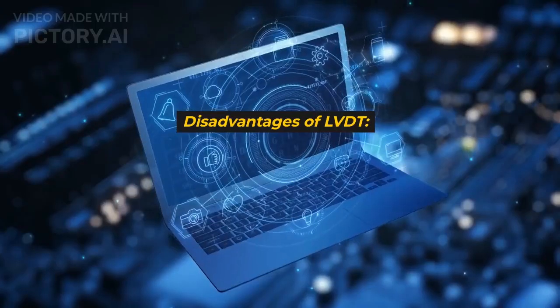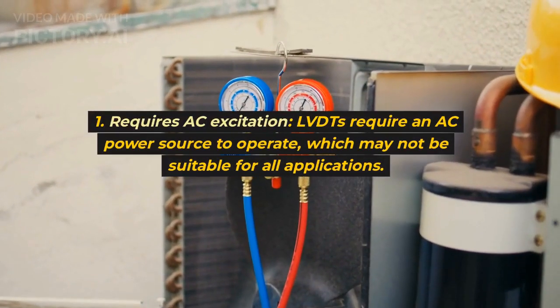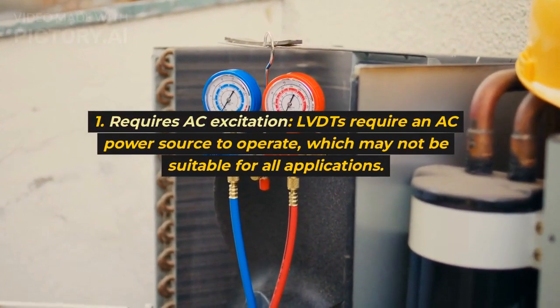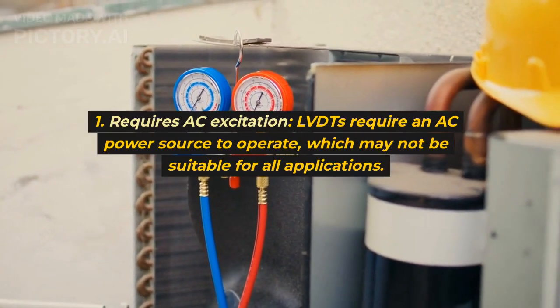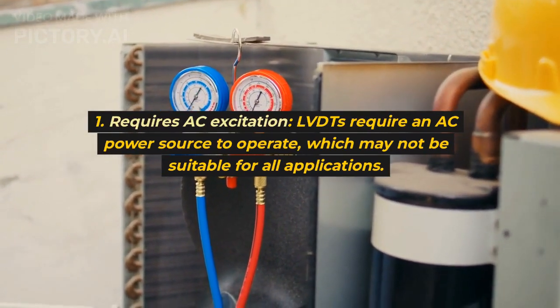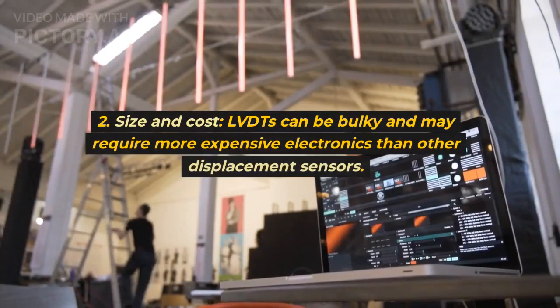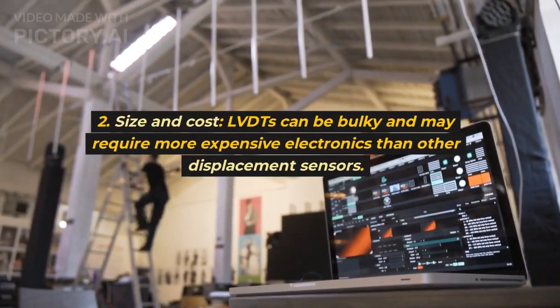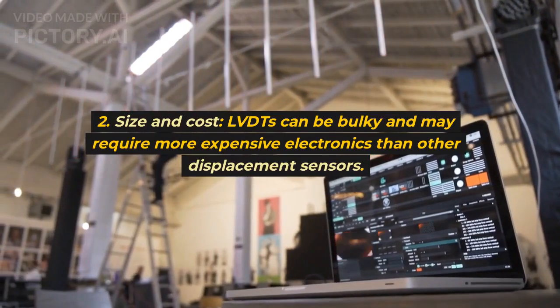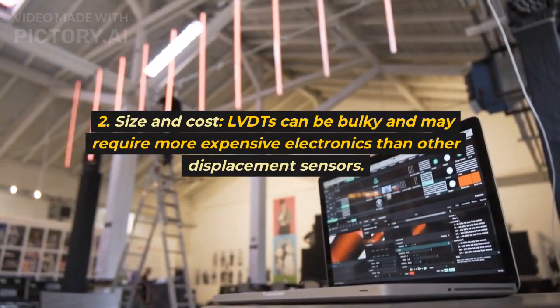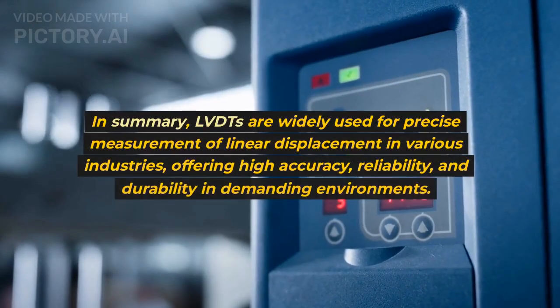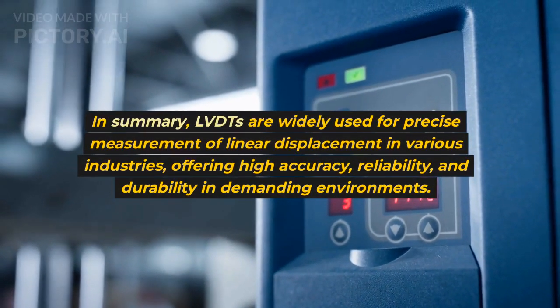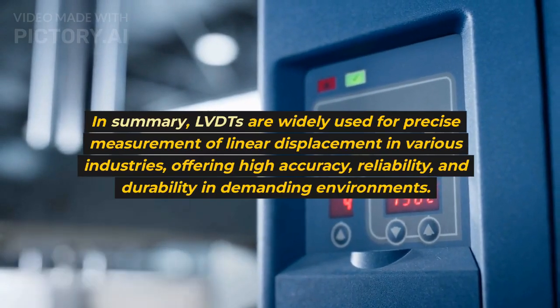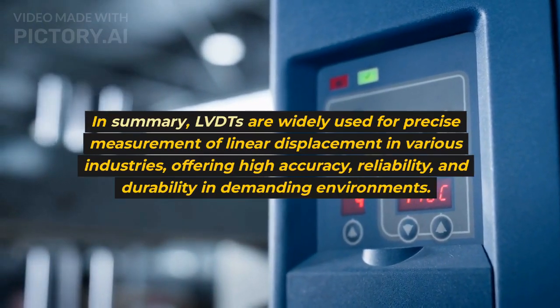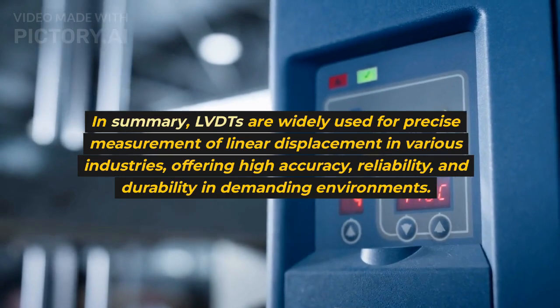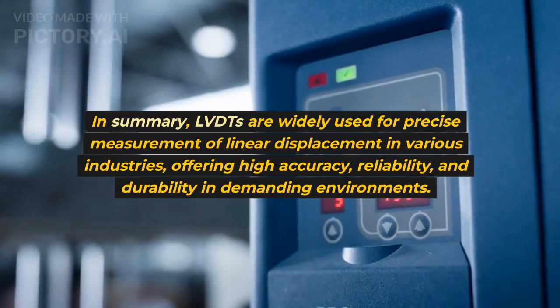Disadvantages of LVDT. 1. Requires AC excitation. LVDTs require an AC power source to operate, which may not be suitable for all applications. 2. Size and cost. LVDTs can be bulky and may require more expensive electronics than other displacement sensors. In summary, LVDTs are widely used for precise measurement of linear displacement in various industries, offering high accuracy, reliability, and durability in demanding environments.